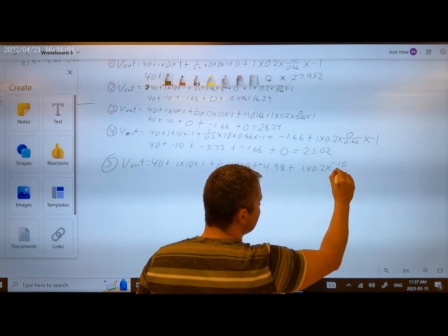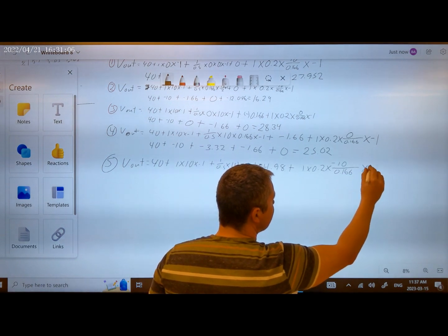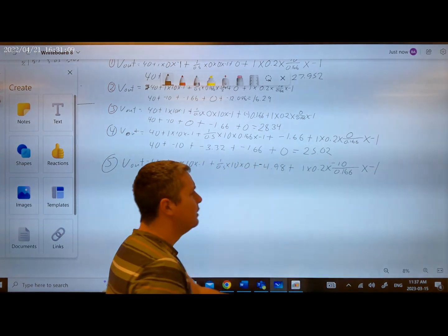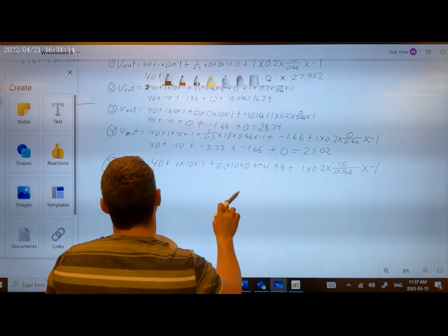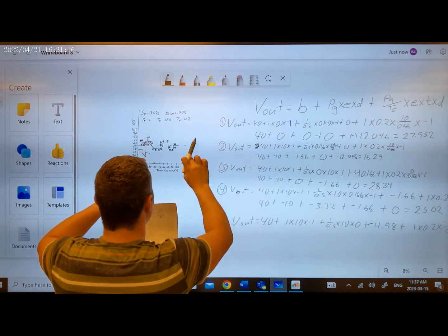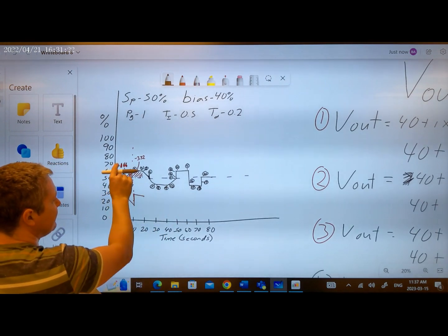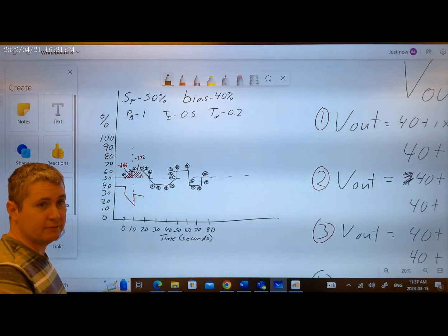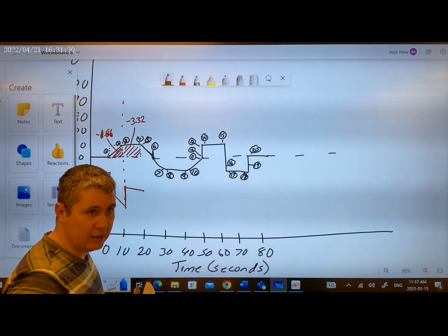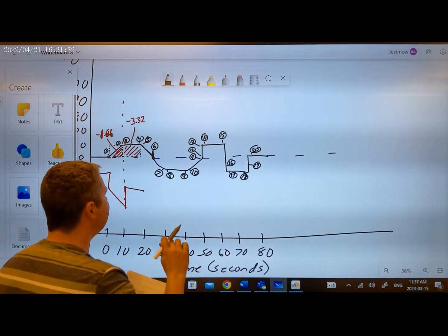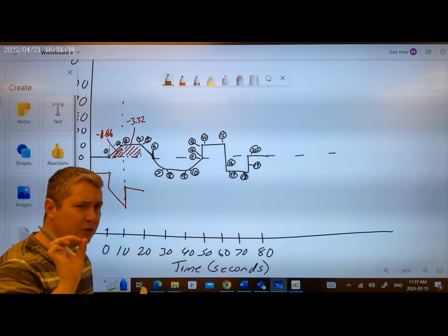That is a minus 10 over 0.166, which is our time, times minus 1, our direction. That's a minus 10 because, remember, we look at this here, our error goes from 60 to 50, right? Before, now we're talking about ramp rate, okay? We're not talking about the difference between our set point and our process variable. We're talking about the ramp rate.